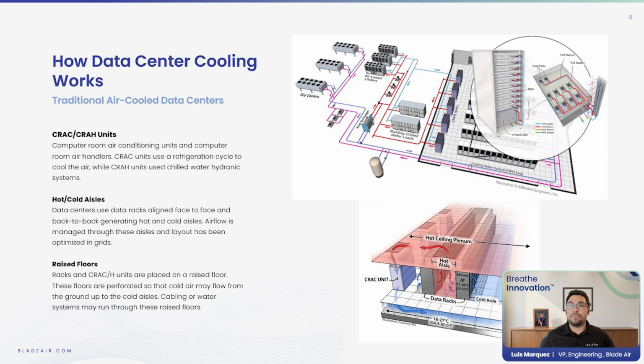Let's take a step back and look at how air-cooled data centers work. Traditional data centers usually consist of a computer room air conditioning unit, or CRAC unit, or a larger computer room air handler unit, called a CRAH unit. CRAC units are used in smaller systems and use a refrigeration cycle with compressors to cool the air, while CRAH units are larger and centralized, using chilled water hydronic heat exchangers to push air through. You can think of CRAC units like the air conditioning systems in a house, and CRAH units like the central cooling used in condos and high-rise buildings.